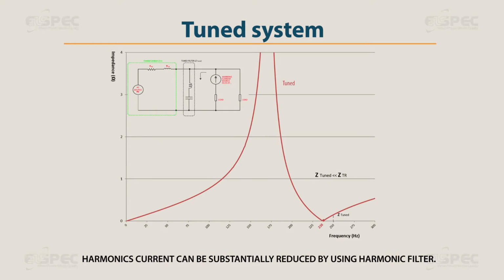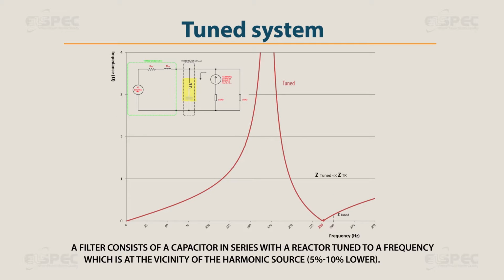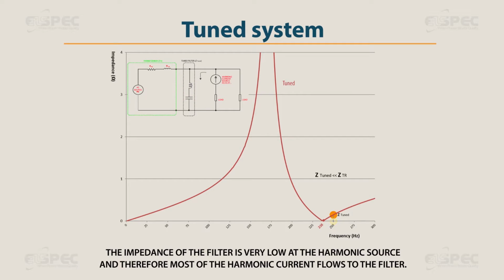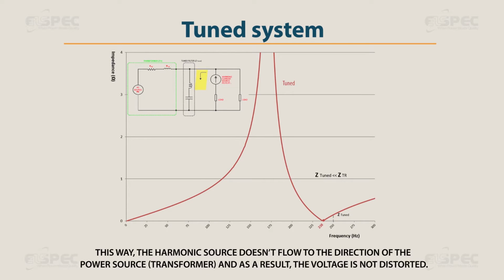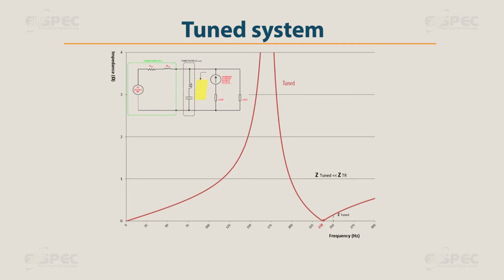Harmonics current can be substantially reduced by using a harmonic filter. A filter consists of a capacitor in series with a reactor tuned to a frequency which is in the vicinity of the harmonic source, 5% to 10% lower. The impedance of the filter is very low at the harmonic source, and therefore most of the harmonic current flows to the filter. This way, the harmonic current doesn't flow in the direction of the power source, the transformer, and as a result, the voltage is not distorted.